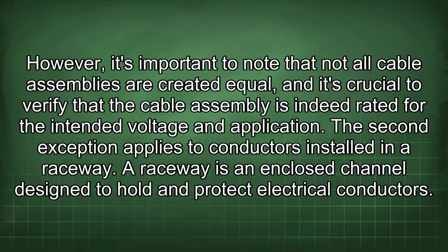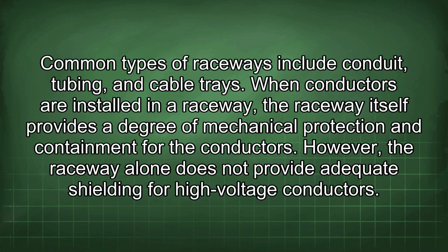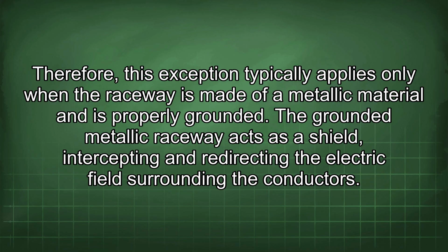The second exception applies to conductors installed in a raceway. A raceway is an enclosed channel designed to hold and protect electrical conductors. Common types of raceways include conduit, tubing, and cable trays. When conductors are installed in a raceway, the raceway itself provides a degree of mechanical protection and containment for the conductors. However, the raceway alone does not provide adequate shielding for high-voltage conductors. Therefore, this exception typically applies only when the raceway is made of a metallic material and is properly grounded.